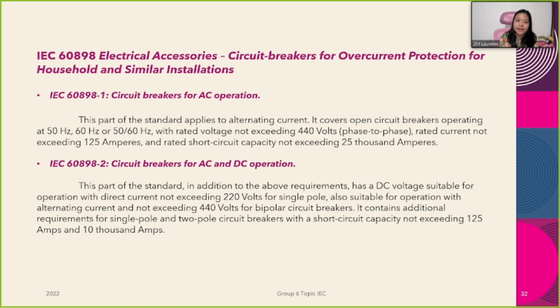For IEC 60898-2, ito naman yung mga circuit breakers for AC and DC operations. So this part of the standard, in addition dun sa -1 natin, is meron din siyang DC voltage suitable for the operation with direct current not exceeding 220 volts for single pole. Also, suitable siya for operation with AC and not exceeding 440 volts for bipolar circuit breakers. And it contains additional requirements para sa mga single pole and two pole circuit breakers with a short circuit capacity not exceeding 125 amperes and 10,000 amperes.